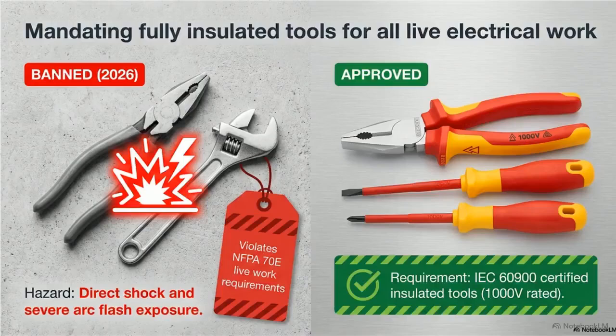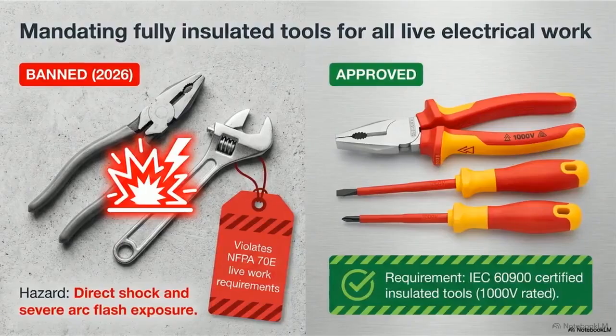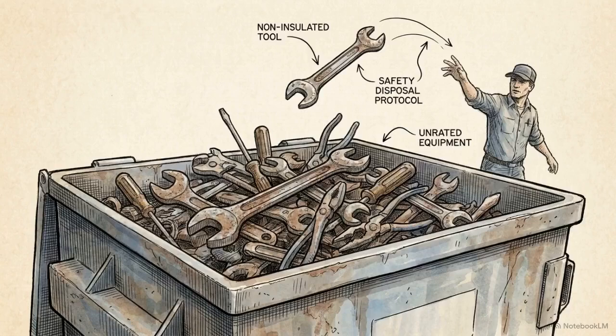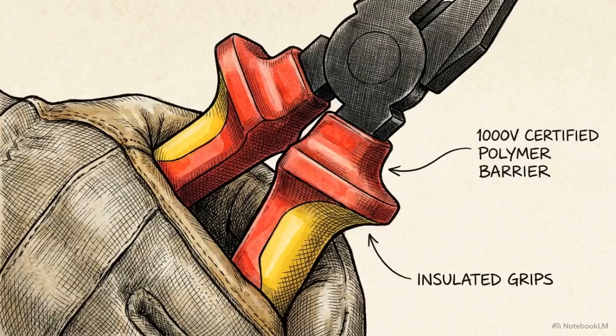That ban extends to bare metal wrenches and pliers on the left, which create immediate exposure to direct shocks and severe arc flashes. Instead, as shown on the right, any tool used near live power must be IEC 60900 certified, tested to withstand 1000 volts. Every unrated hand tool needs to be physically removed from the facility today. Certified insulation is the only acceptable barrier between you and live voltage.